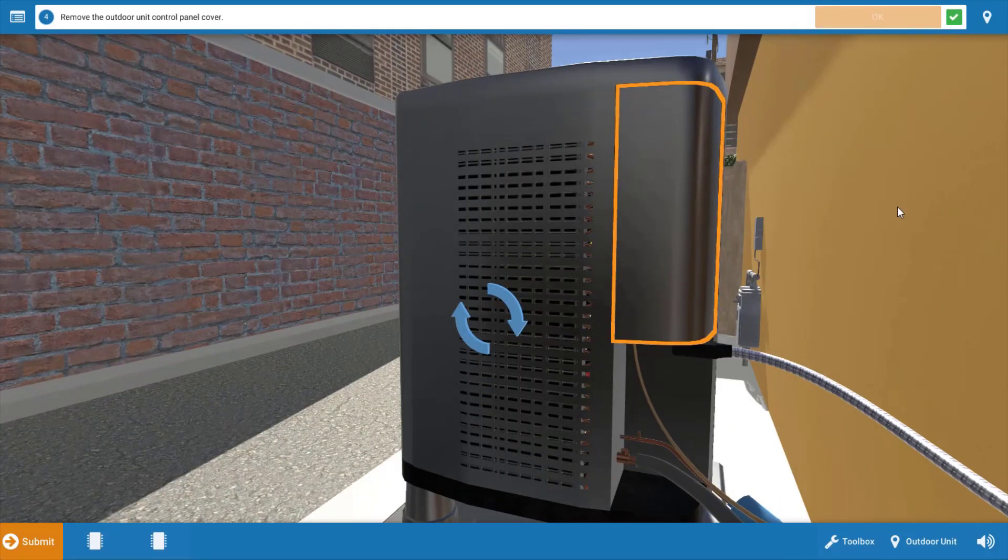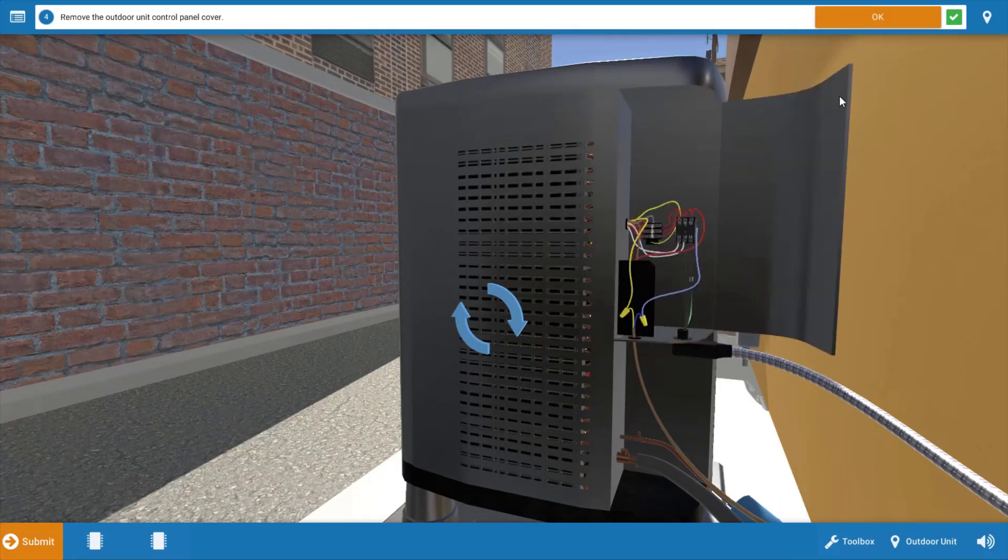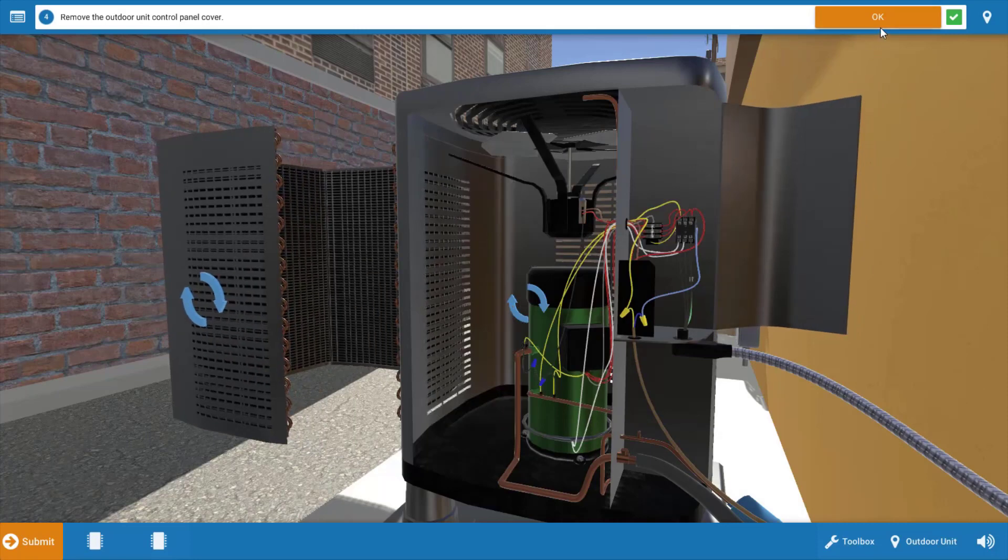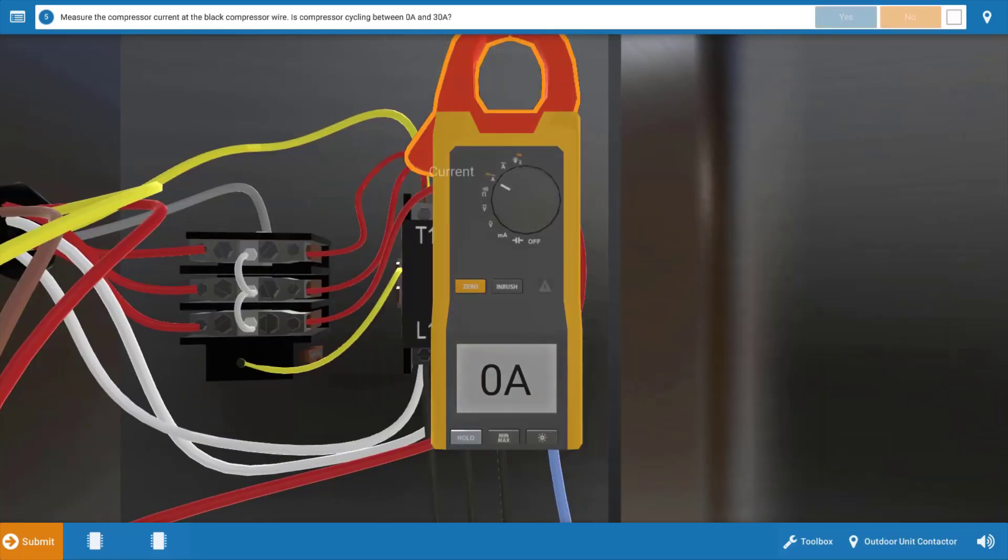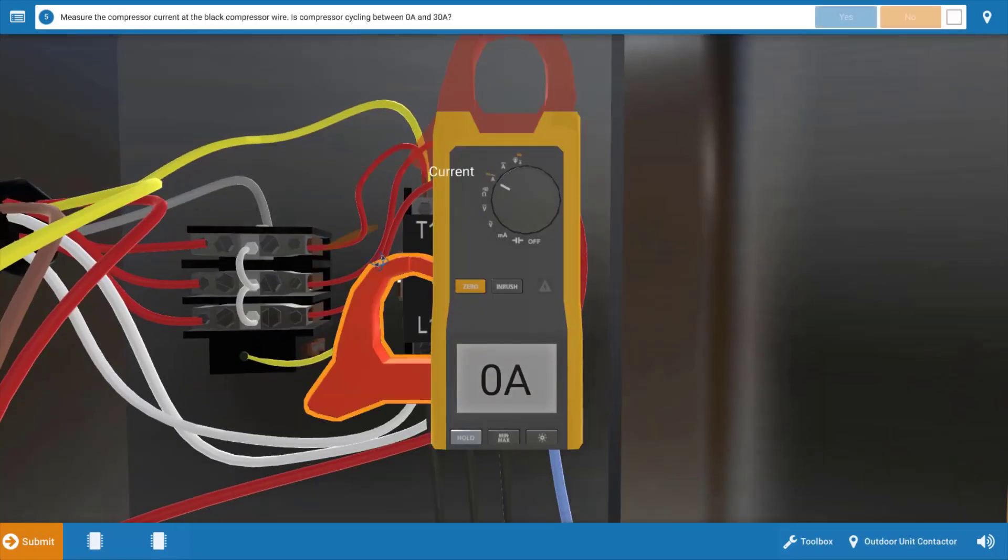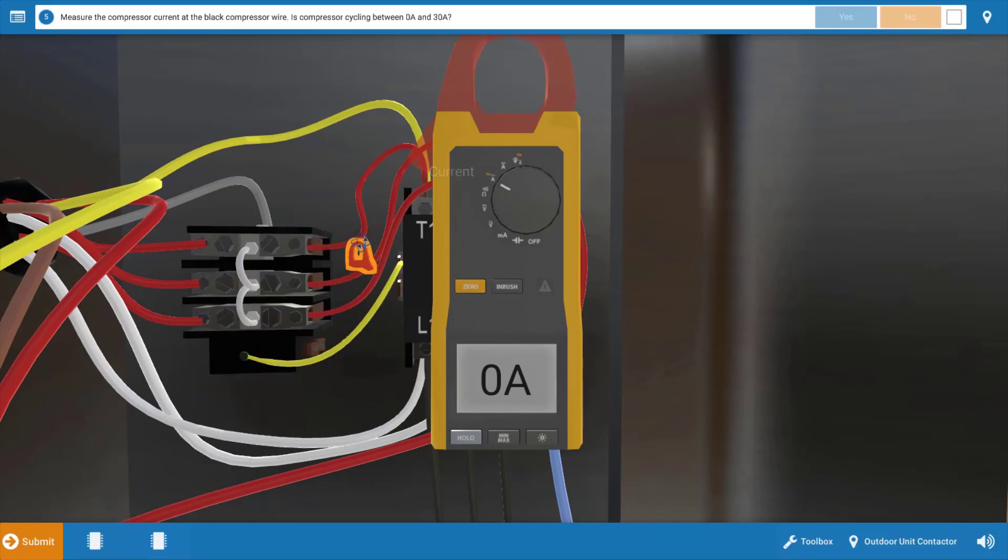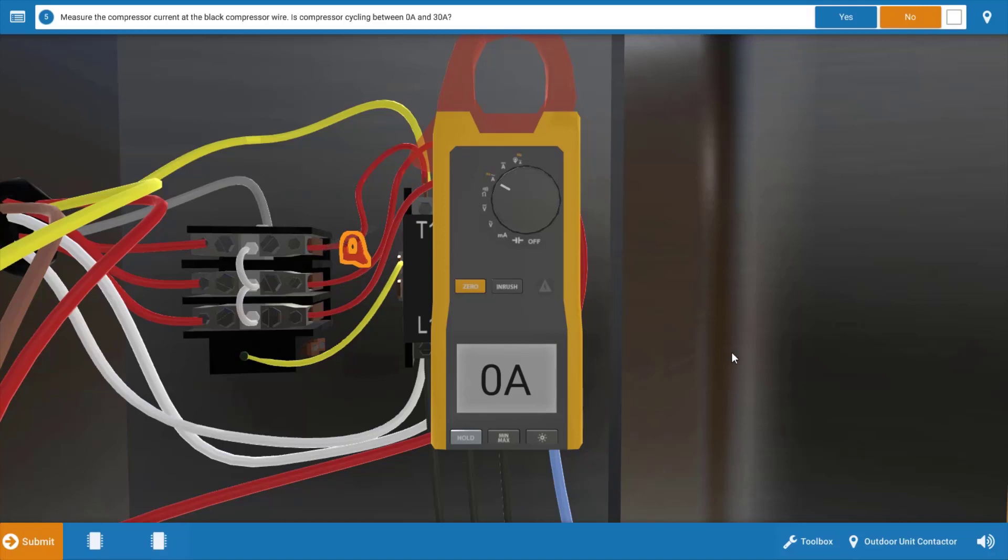Next we need to investigate the compressor. We're going to open the control panel, click yes or okay on the procedure guide, and we're going to measure the current draw of the compressor. We're just going to clip the jaws around one of these wires, and we want to determine if the compressor is cycling on and off or if it's just off. In this case we have a steady zero amps, which indicates that the compressor is off, so it's not cycling.